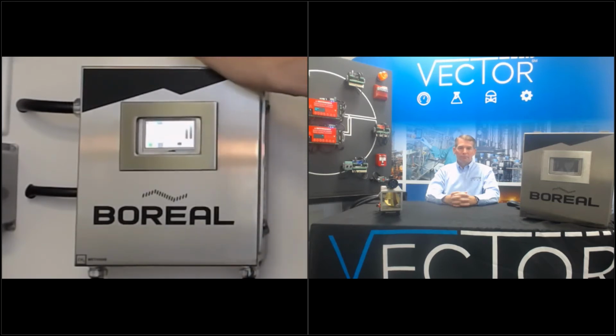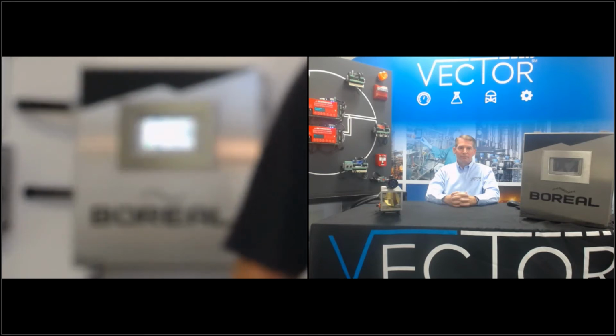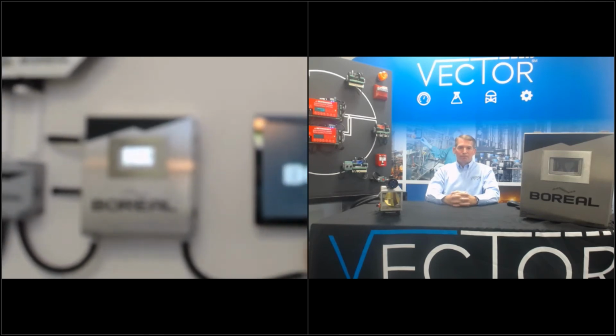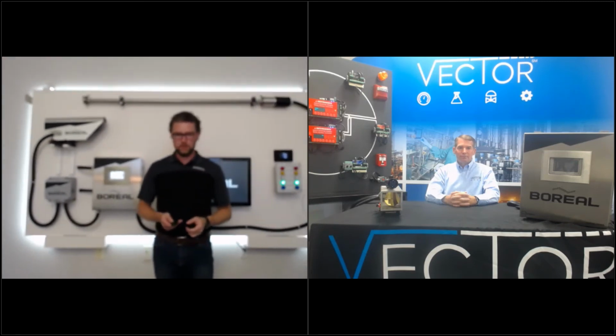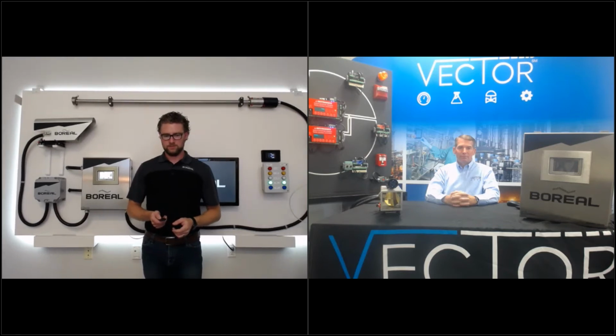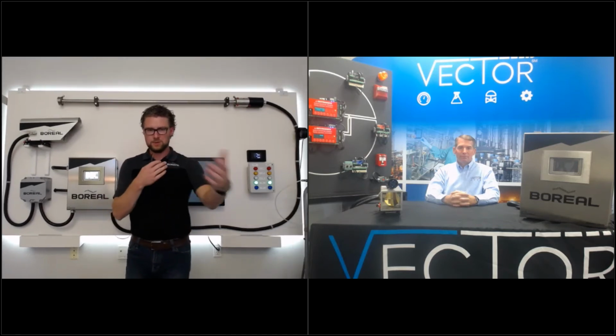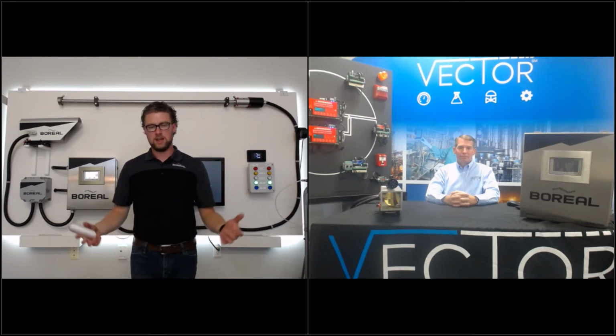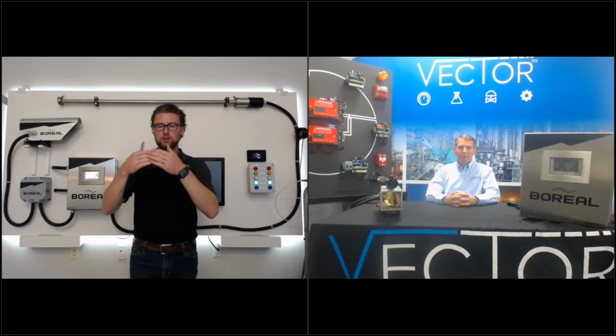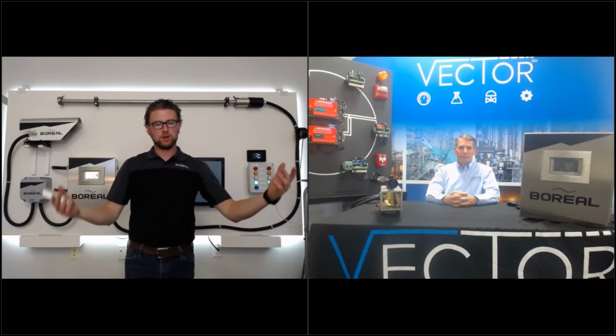I'll show you, there's a light bar here that shows the different variations as to what it handles with these particular light level arrangements. For this particular technology, there is a functional test where we use an opaque piece of glass that has a special coating on it called a neutral density filter. That functional test demonstrates how much transmittance this system can handle. Our system and our technology can handle up to 97% beam block. So we can operate with only 3% of returned laser light back and still have our plus or minus 2% accuracy reading and functionality as well.